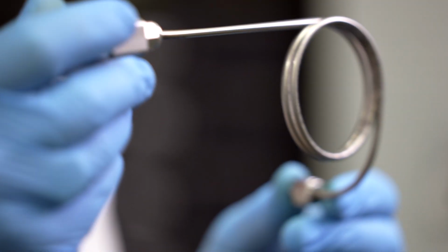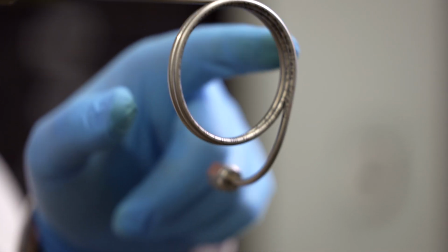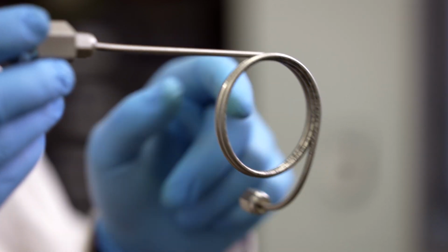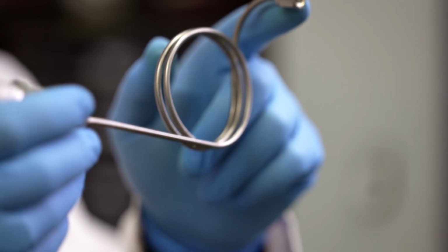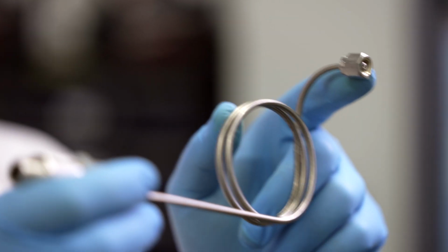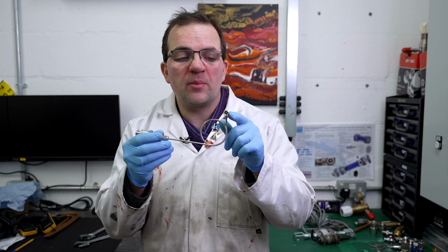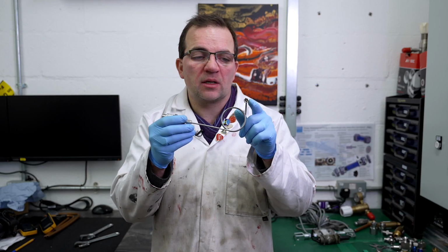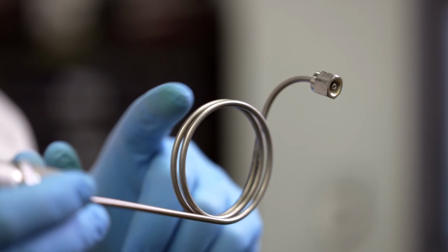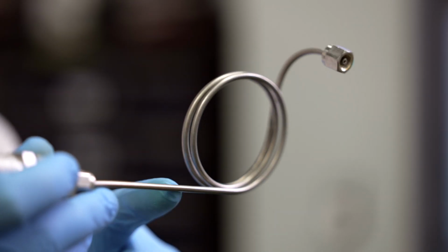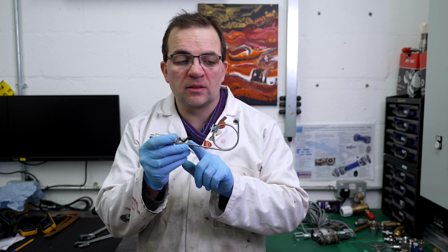What you'll also notice on this particular piece of assembly is that we've put a pigtail in. The reason you might want to consider putting a pigtail in is if the gases coming into the pipe assembly are very hot. For instance, this sub-assembly might be connected to your rocket engine combustion chamber, so the hot gases have a long distance to travel before they get to the pressure transducer, and so there is a cooling effect.